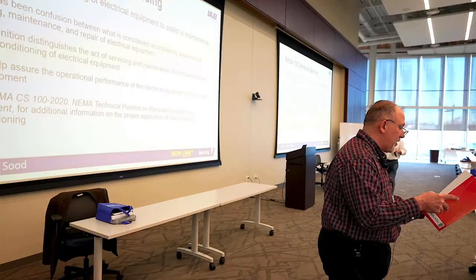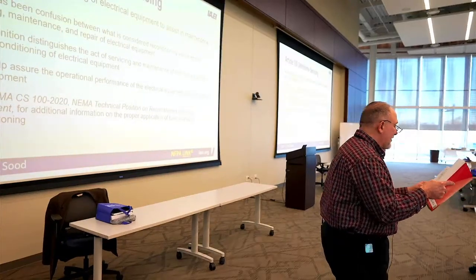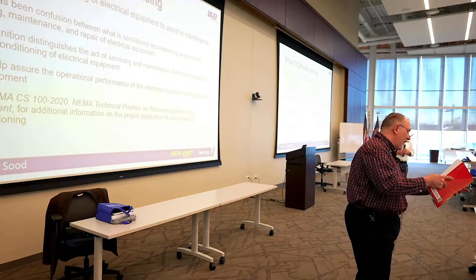It says identified replacement parts verified under applicable standards that are either provided by the original equipment manufacturer, or designed by an engineer experienced in the design of replacement parts for the type of equipment being reconditioned. So you've got options, both of those, right? Now you have A, B, and C, first level subdivisions.